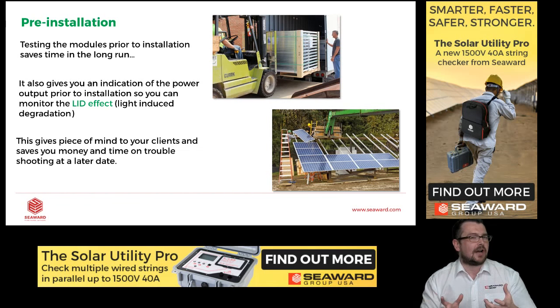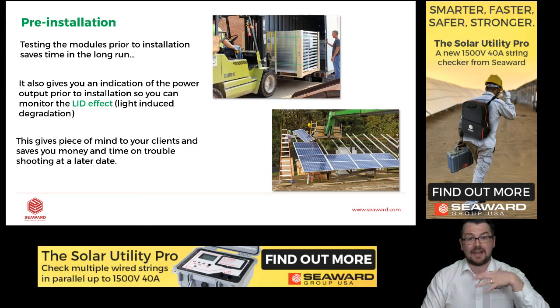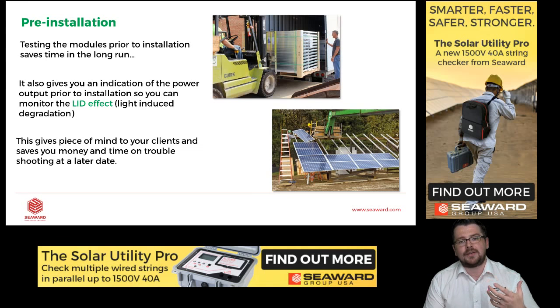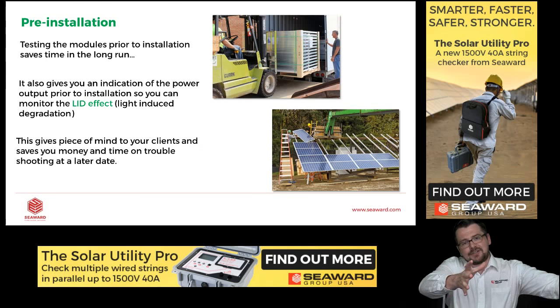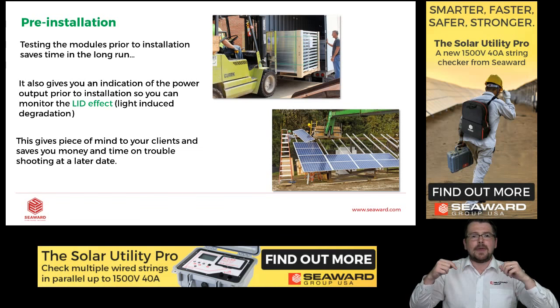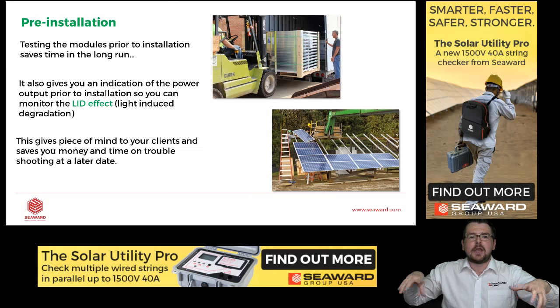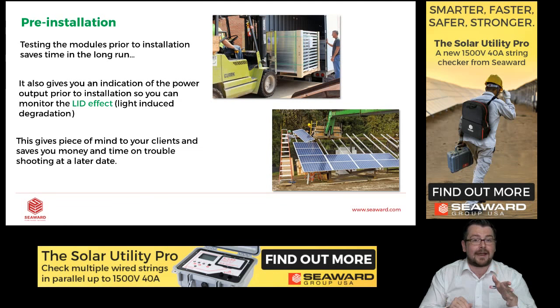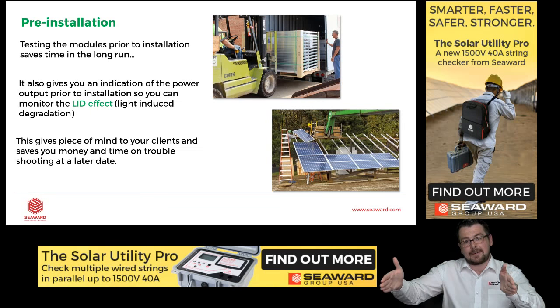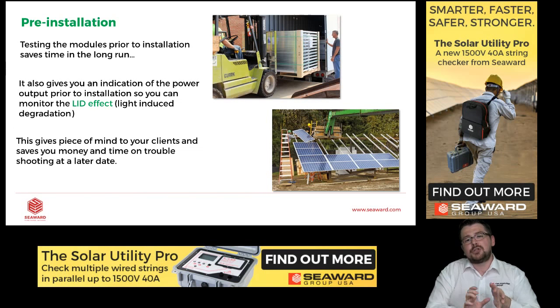So when would you use IV curve tracing? Well, there are a couple of stages in the life cycle of a PV system when it's useful. One point is the pre-installation phase. This is as the modules are coming off the back of the transport, you may want to do a couple of curves on a couple of panels. I'm not telling you to do curves on every single panel before they're installed, but say you had a sample set of one panel in every 10 pallets. This would give you a good indication if there's any manufacturing fault with that batch, because generally when the pallets are kept together from the factory, they're not separated often. So if you can catch one bad panel in a batch, that might suggest that the rest of that pallet has the same manufacturing fault.